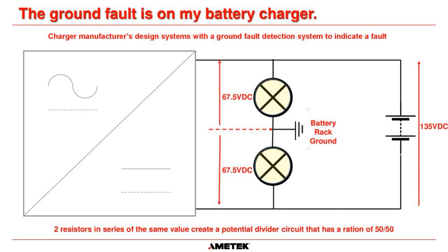Now, in normal circumstances, both lamps are going to be half lit, because two resistors in series of the same value create a potential divider circuit that has a ratio, not a ration, sorry, I need to fix that, a ratio of 50-50. So that means you're going to get 67.5 volts for a 135 volt DC system. You're going to get 67.5 volts across that lamp and 67.5 volts across that lamp. Okay? So they're going to be half lit. I wouldn't say dimly lit, so they're going to be half lit.